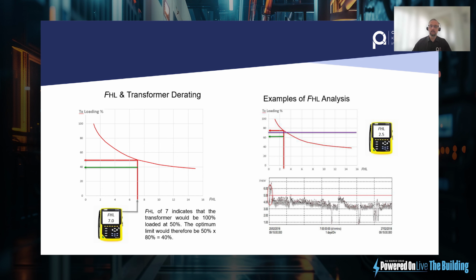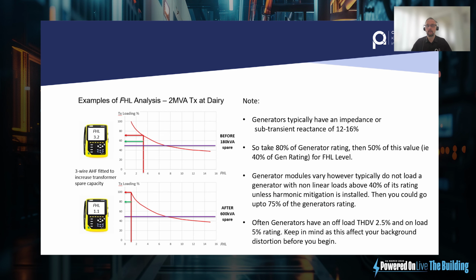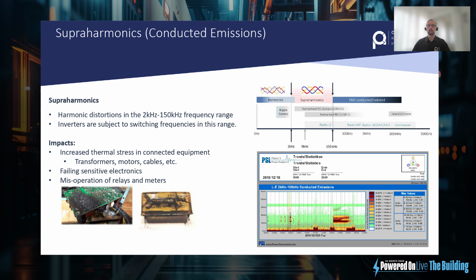And here's a live example of that. If we look at this one here, here's a dairy where they have a 2 MVA transformer, and their spare capacity was only 180 kVA for more loads that they were looking to put on because they had an FHL of 3.2 that we measured. We installed a harmonic filter, which reduced the mitigation down to 1.1, which meant they had an additional 600 kVA for their future loads. So again, that's a whole topic in itself. I don't want to bore you with too much of that, but the importance of getting the harmonic reduction down means that your transformer that's supplying you can keep delivering you the loads you require.